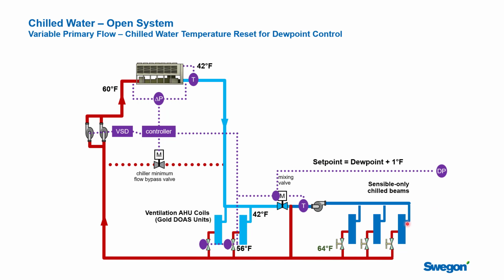And that would mean that the moisture in the air would start to condense on any exposed chilled water piping, and it would start to condense on the coils that are actually in the chilled beams. This is a very serious situation. It's not supposed to happen, but if it does, we need to have a response in the building controls to deal with that. You could do things like, if you see high humidity in a zone, just shut these valves off and kill the flow to that chilled beam so it doesn't sweat. But if you do that, you are turning off the air conditioning in a control zone that is now probably hot and humid and probably needs air conditioning more than ever. You won't condense and sweat in the space, but you're also providing no cooling relief to the occupants.